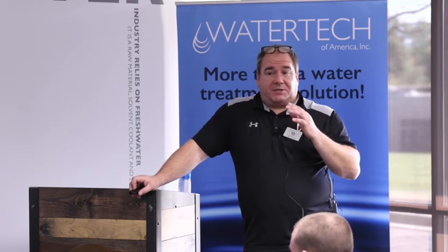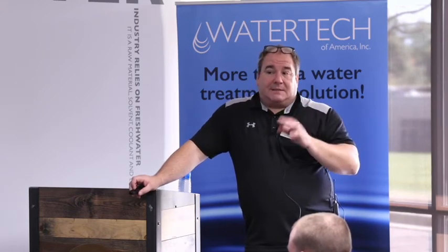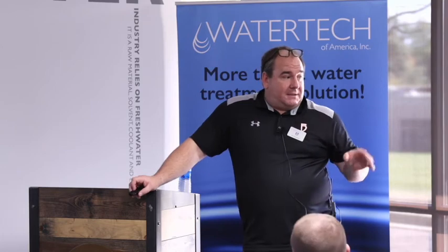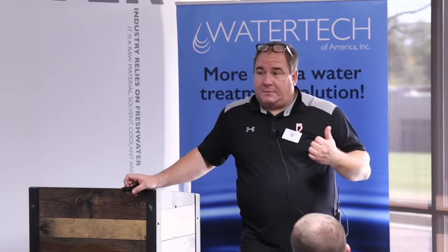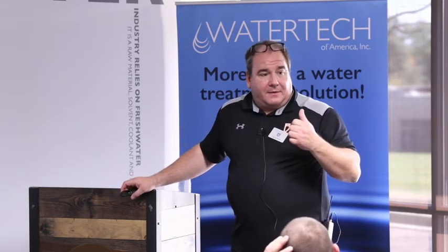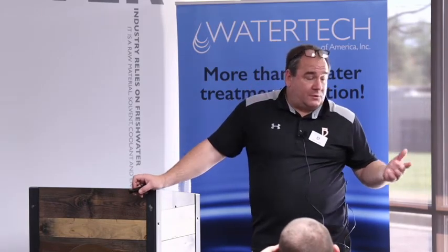Obviously, these are things you've got to check when it's down, when you have a chance to inspect it. Nozzles get clogged because, remember, we've got iron coming back, or dirt or debris could come back. It could come from the pretreatment system too.